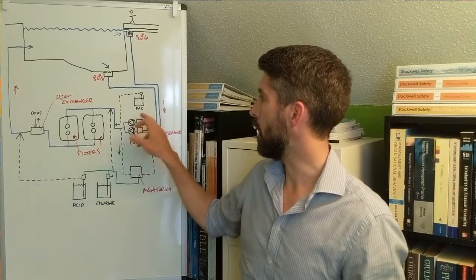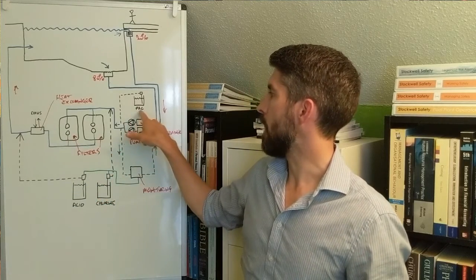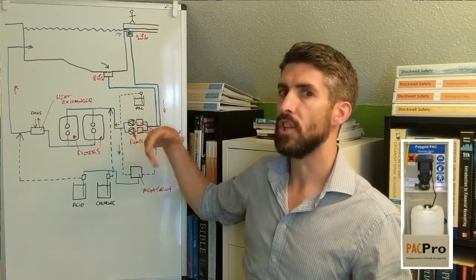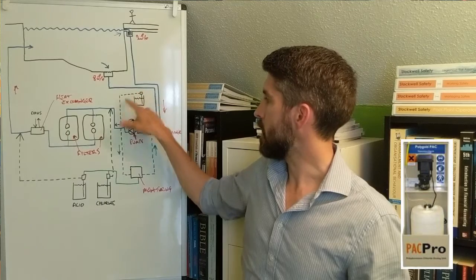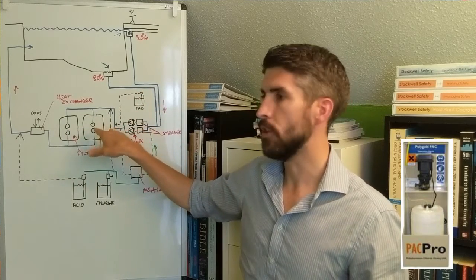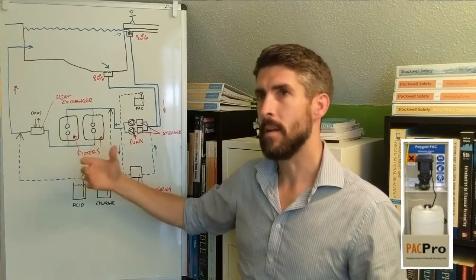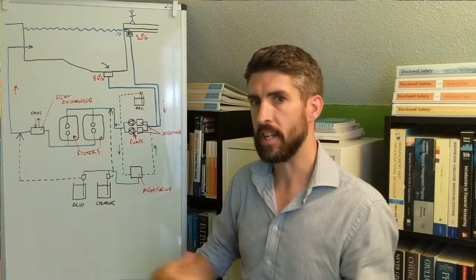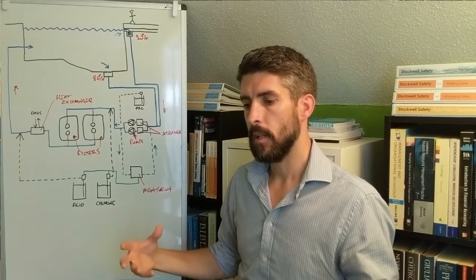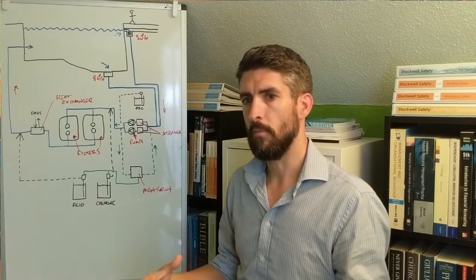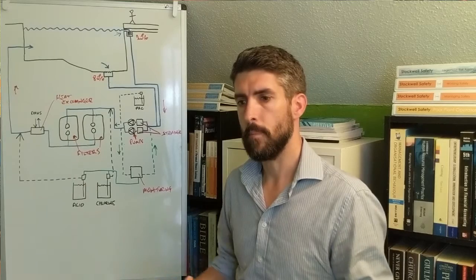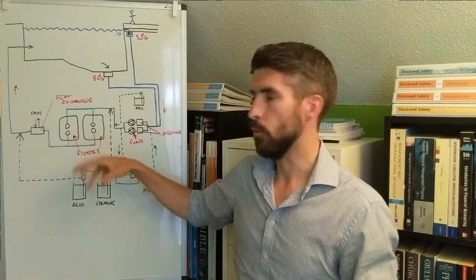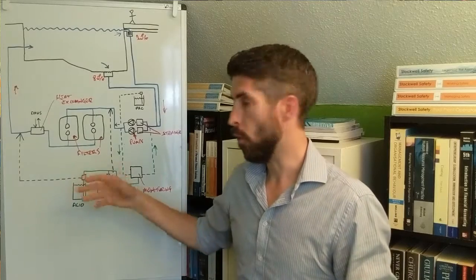Having knowledge of where your chemicals are being dosed is extremely important. What I've also got here is PAC, poly aluminum chloride, which is a coagulant that is being dosed in prior to the filters. It basically helps the filters by flocculating or coagulating very small particles of pollution into larger flocs, so that the filters are able to retain more pollution that way.